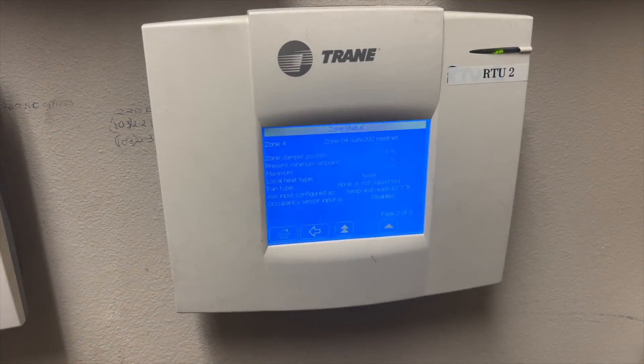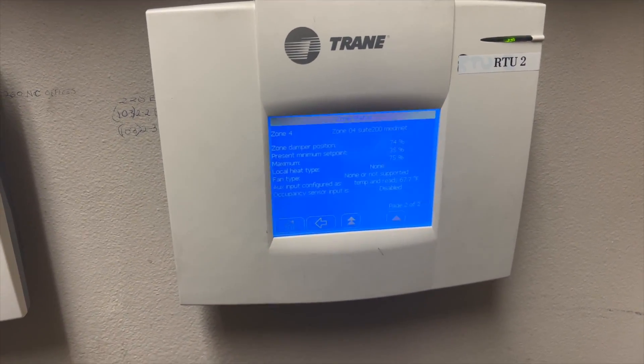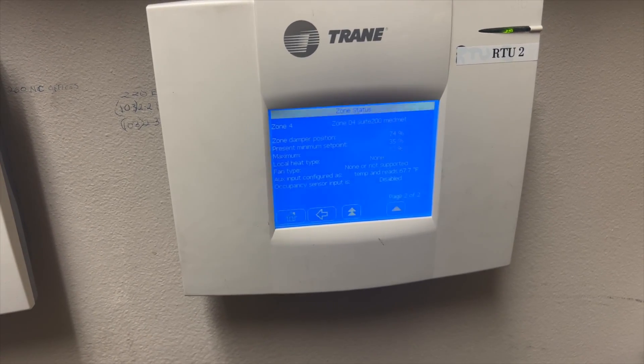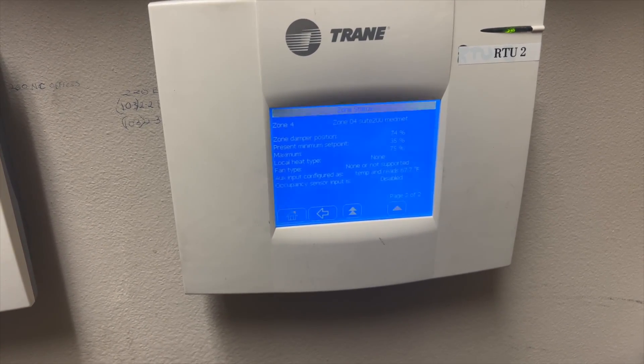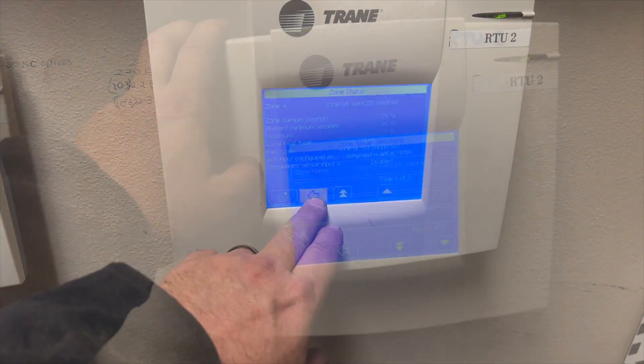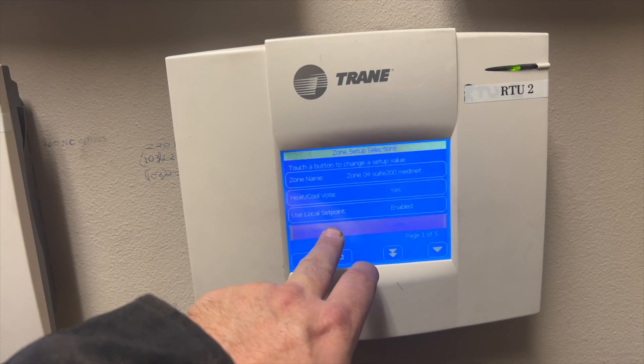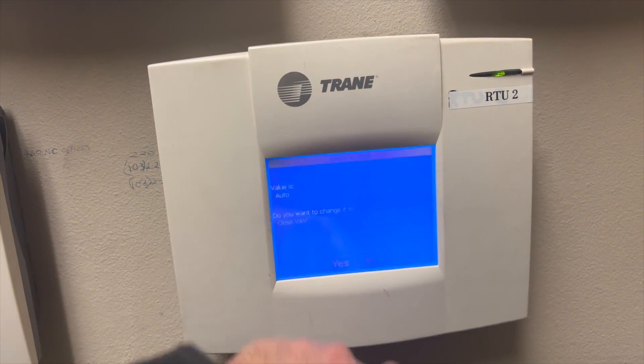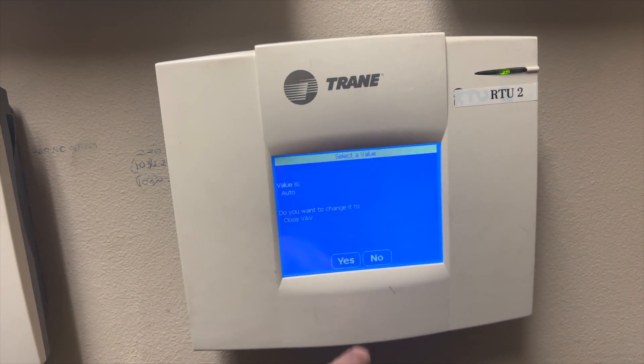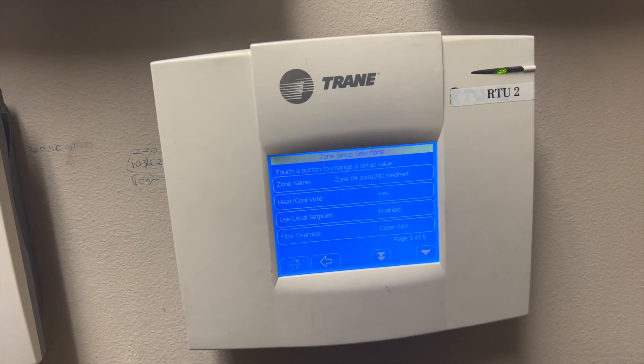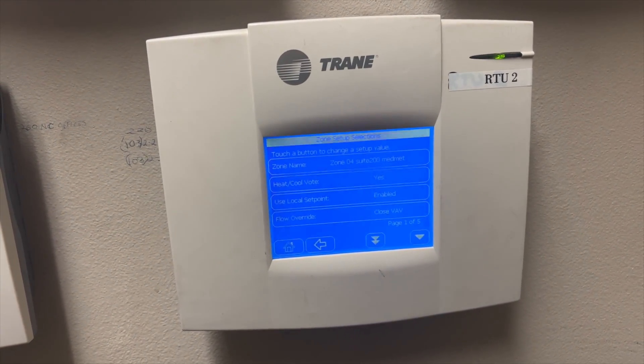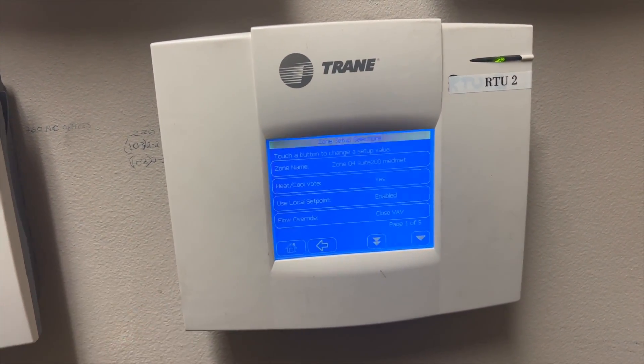I think maybe the damper's messed up, so we'll go ahead and try to turn it off manually. Flow Override — we want to close our VAV. I just want to make sure it's actually working, so the noise should stop. Let's go check it. Our damper works.